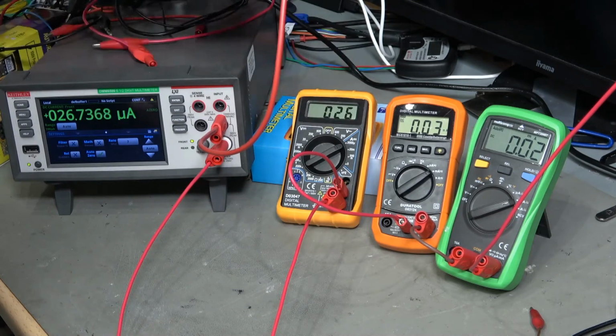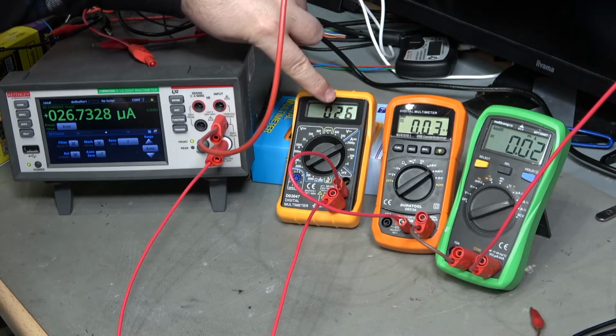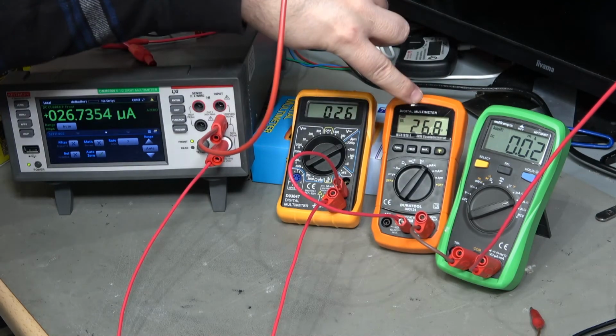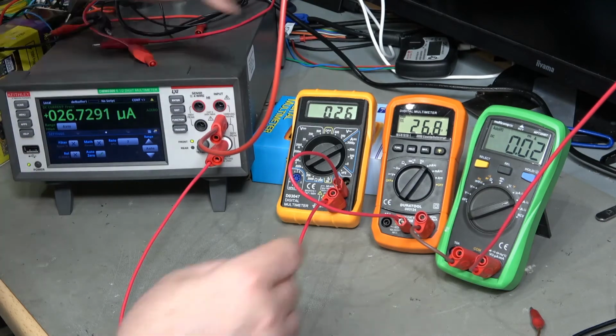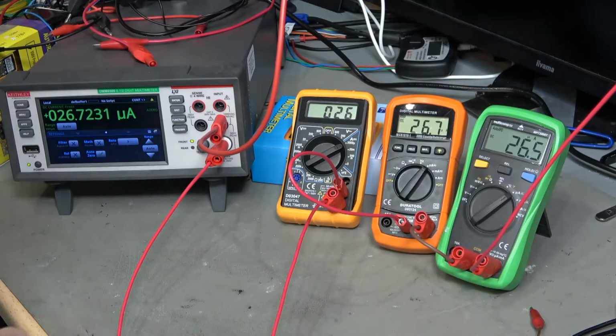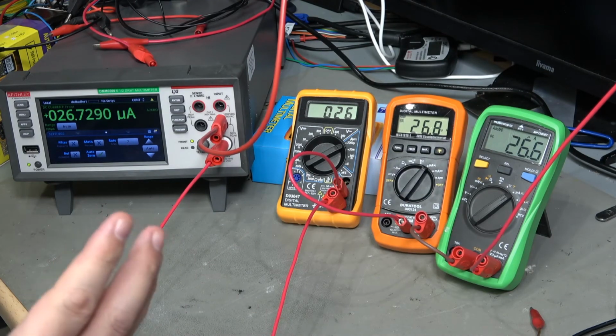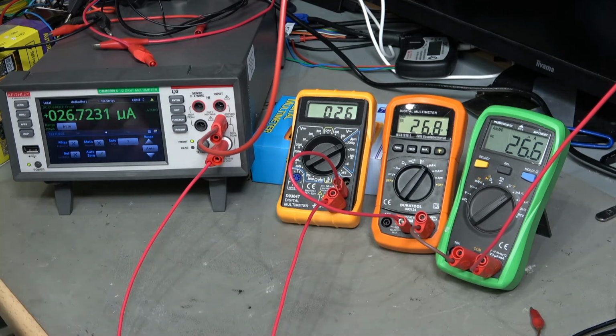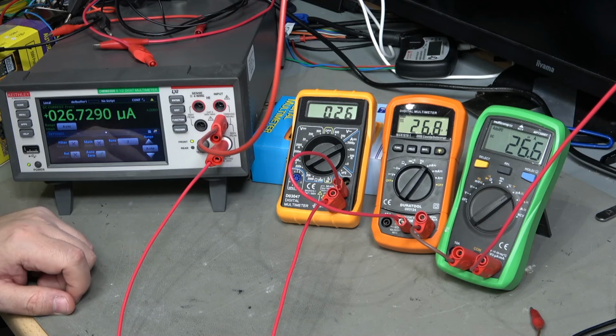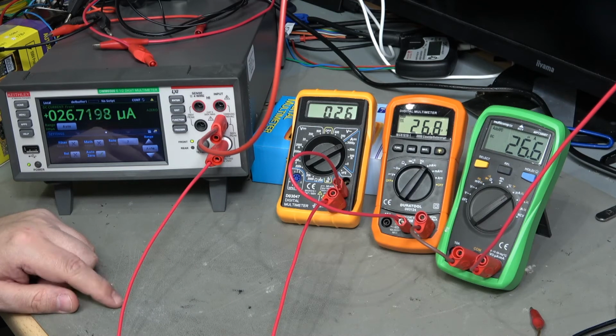So we'll turn this on to 2000 microamps and we can see it's reading 26 microamps. Pretty bloody good. Turn this one down to microamps. 26.7. Well, 26.8, okay. Microamps. 26.6. So even right down at those ridiculously low currents, I mean 26, 27 microamps is nothing. Could you go lower than that? Probably, but I'd have to set up some different test gear in order to do it.